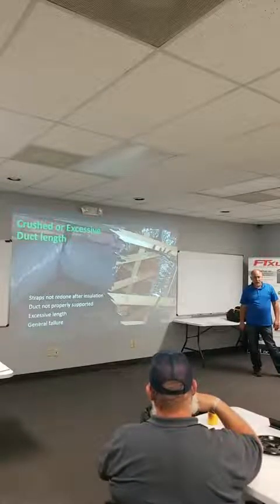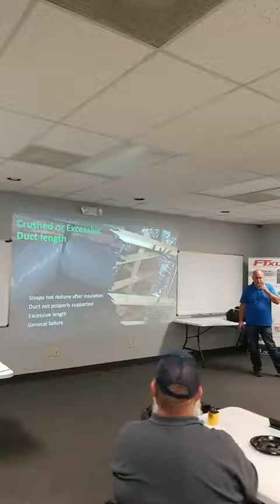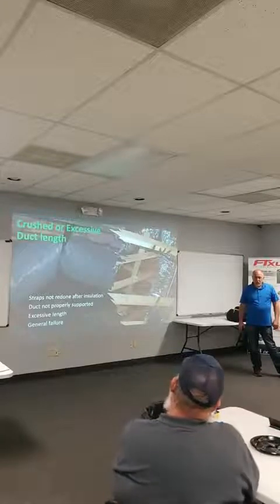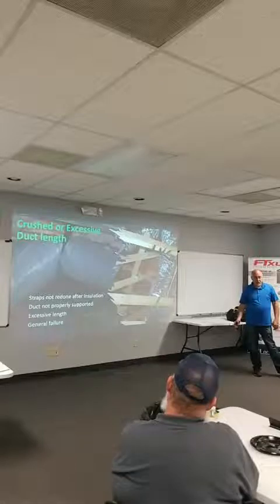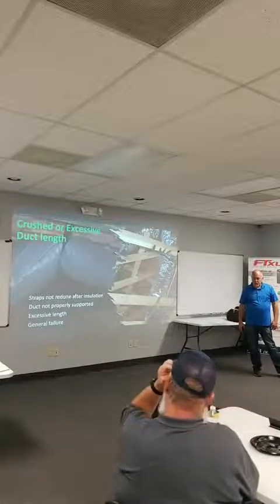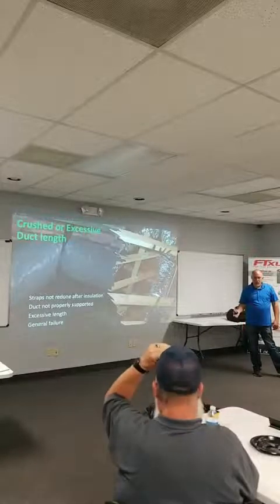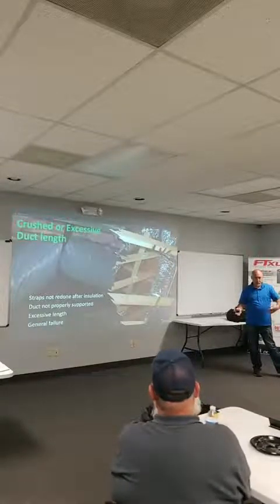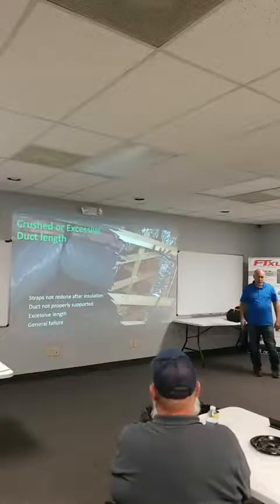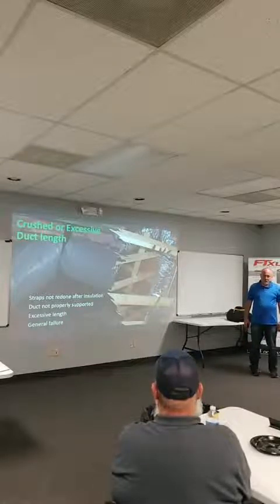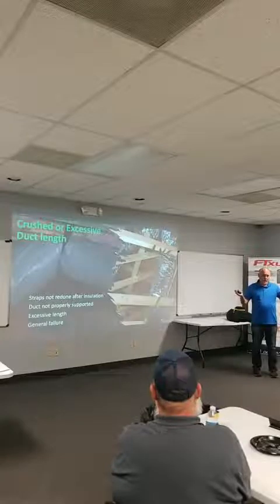I'm like, did anybody do a heat loss calculation in here? And they go, no, we just had an upstairs unit, downstairs unit. I'm like, well, let's take a look. So the upstairs unit's in an attic, so I get in the attic. It felt like duct leakage in the attic, because I could feel the pressure difference. I'm like, I think you got duct leakage up here, pretty serious duct leakage. Like, no. I start poking around, I find a hole in the return. I can put my hand down in, so we tape that up.